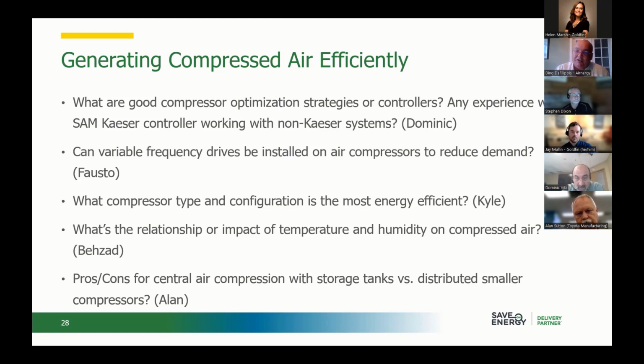Some applications call for higher than normal pressure than the plant can do. So I may have a dedicated piece of equipment that does actually need 120, 130 PSI. Don't run the entire plant at that pressure, regulate as low as you can. And yes, some of them have actually put point of use smaller compressors just to feed that piece of equipment. So again, it's one of those things where you've got to stand back, analyze the system, look at what you have, and then come up with the best scenario.